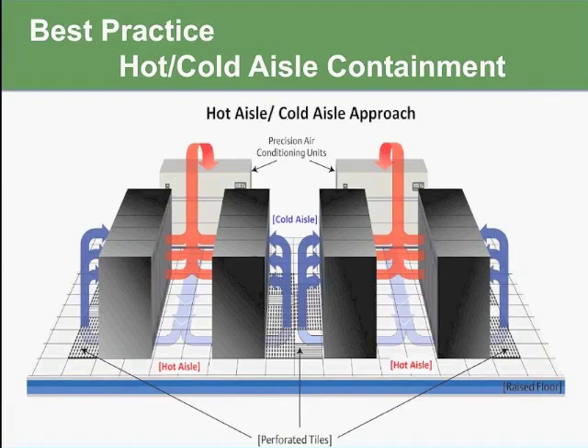So going back to the idyllic picture of what you're trying to achieve with this airflow management is simply that your airflow from the cold aisle goes into your servers, comes out the back end hot, goes directly into the return air for your CRAC unit. Now, an important thing to understand about this perfect airflow is that when you're maximizing the delta between the CRAC unit supply air, the cold air, and the hotter return air, you're actually maximizing the efficiency of the CRAC unit. So you're not only improving the cooling of your servers, but you're also improving the cooling efficiency and the energy efficiency of your CRAC unit.